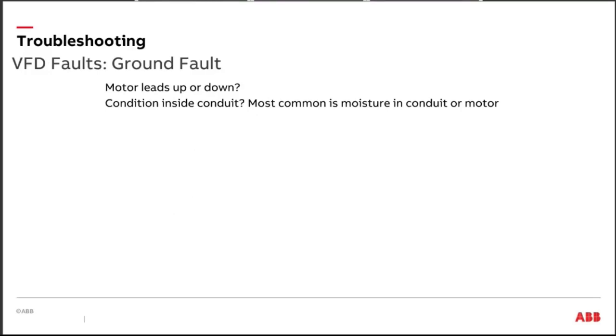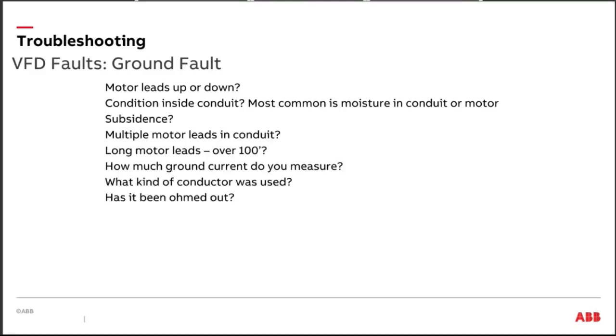In the coal mines, you have to worry about water because everything seeps to its lowest point. So I always like to look and see if my motor leads, if conduits are going down. One of the first things that comes to mind is moisture in the conduit. Subsidence can cause conduits to break, and I can have water in the conduit. Are there multiple motor leads in the conduit? How long is that motor lead? What kind of conductor? Did I use THHN conductors? What is going on that I could be having a ground fault problem?